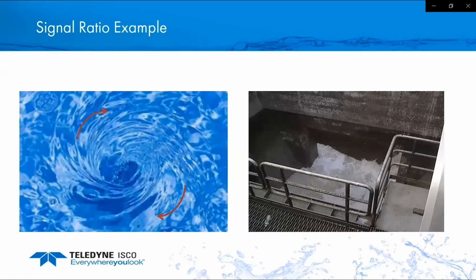So if it starts off with a 100% ratio, everything's going one direction, and then all of a sudden it starts dropping down to 20%, well, I may have some debris or something that's creating a lot of swirling and turbulence. And so that can be an early warning to send a technician out there to do some maintenance, clean the site before you have an actual problem.